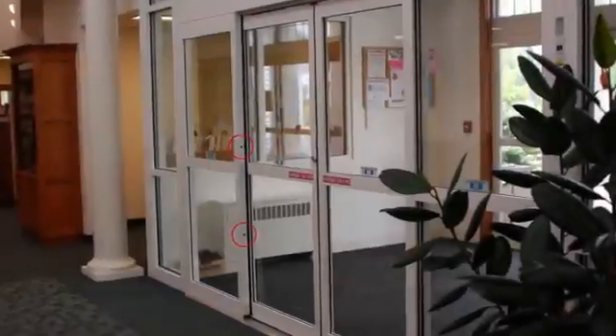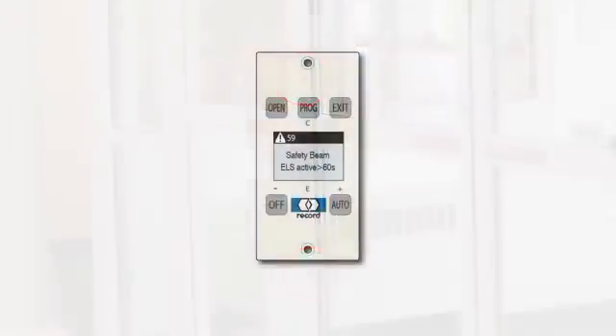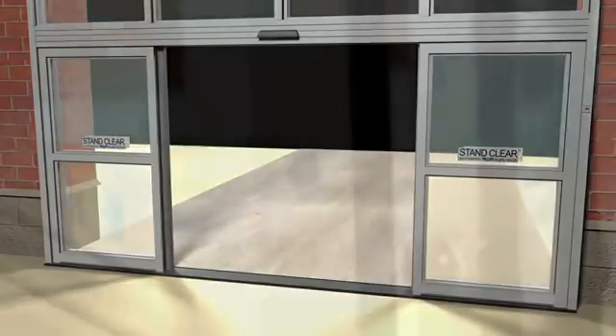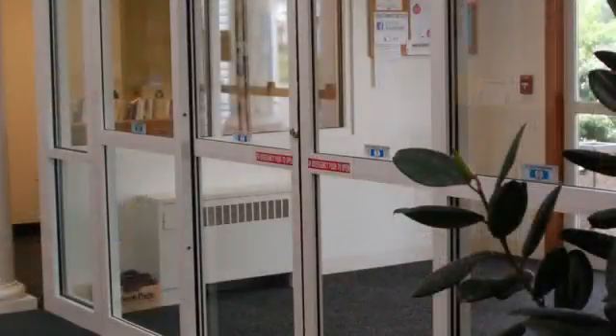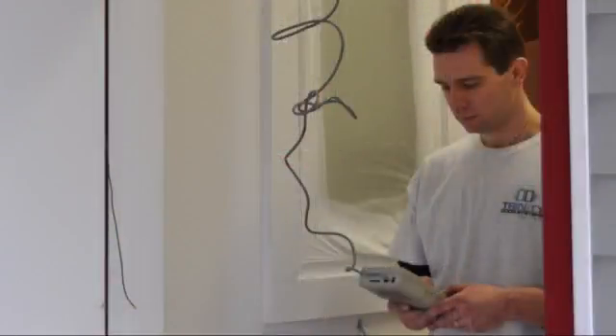Safety beams are installed to add protection inside the door opening. A similar error may be displayed if a safety beam detects an object for an extended period of time. Ensure that the door opening is clear and that the safety beam heads are mounted securely and that they are not covered. Opposing heads should have a clear view of one another. If this error message remains, a service call should be placed with an authorized service provider.